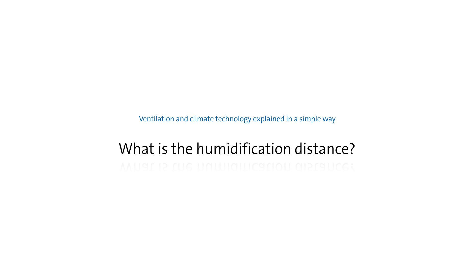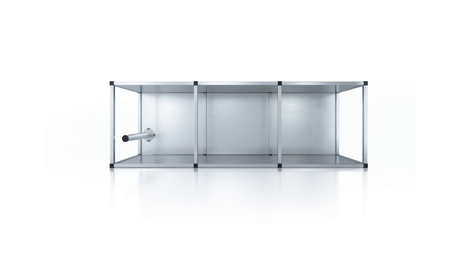Humidification distance. What does it mean? Any steam leaving the steam distribution pipe needs to pass a certain distance until it has been fully absorbed by the air passing through, until it is no longer visible as mist. This distance is called the humidification distance BN and serves as the basis for the calculation of the minimum distances to the components installed downstream.